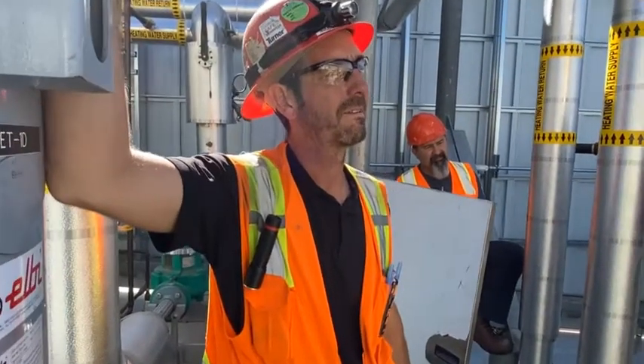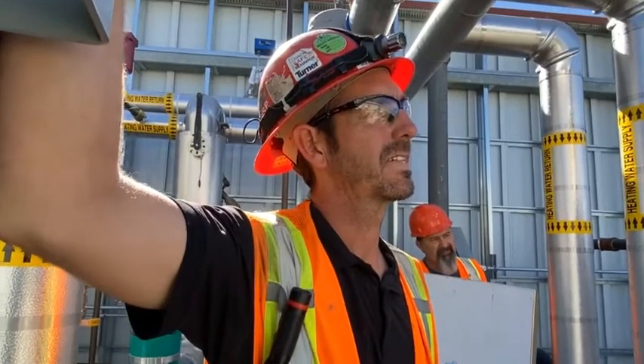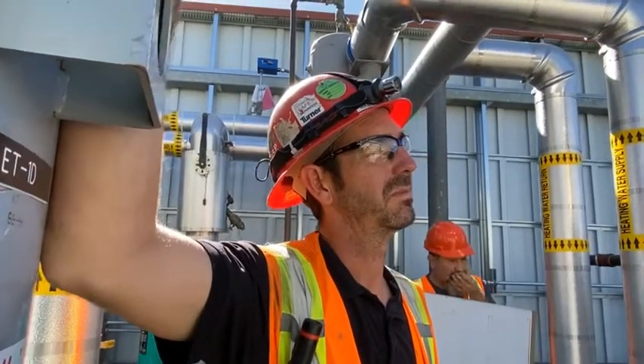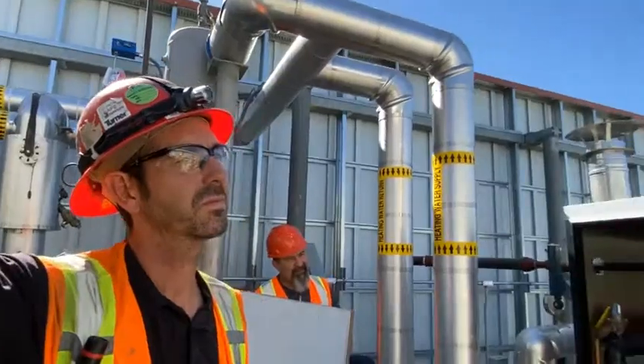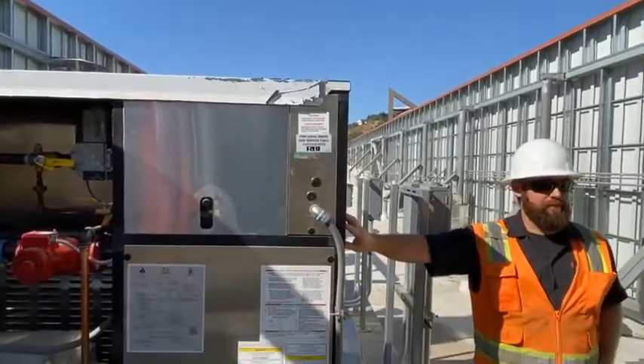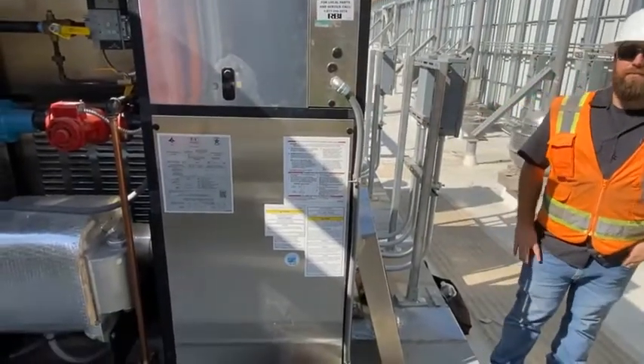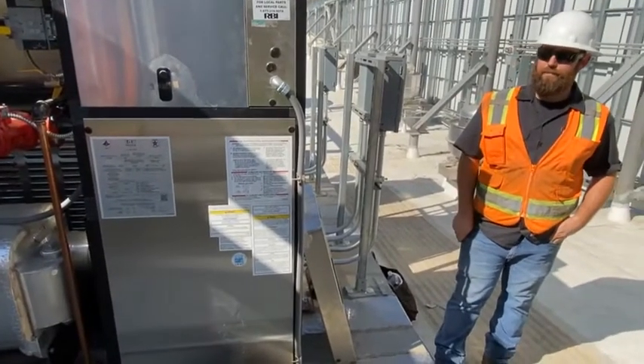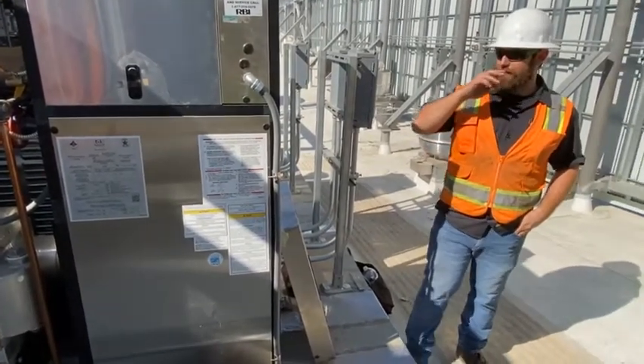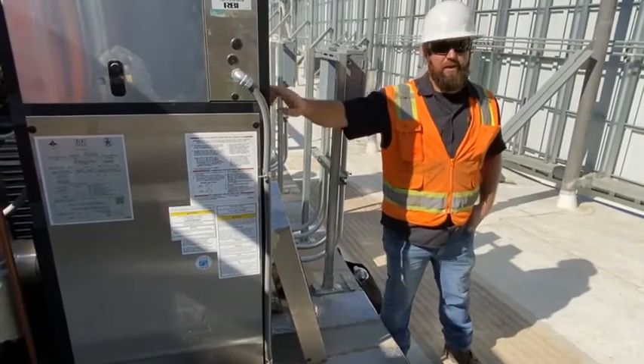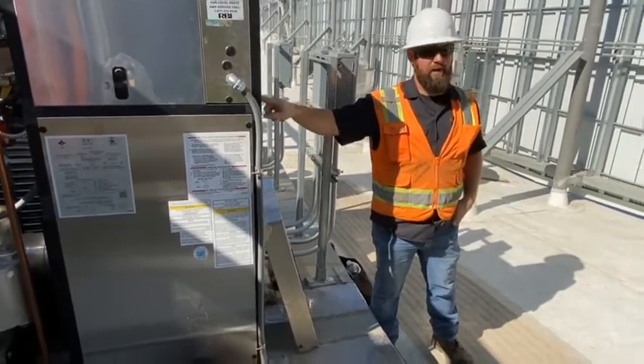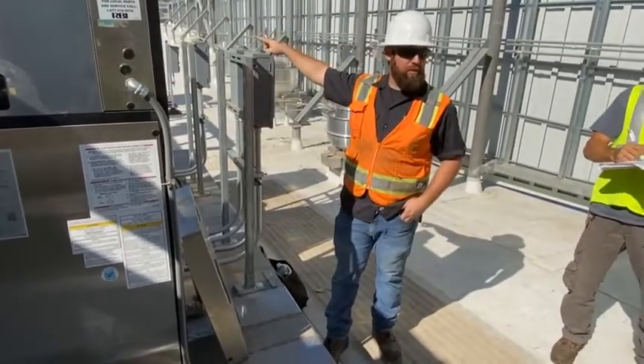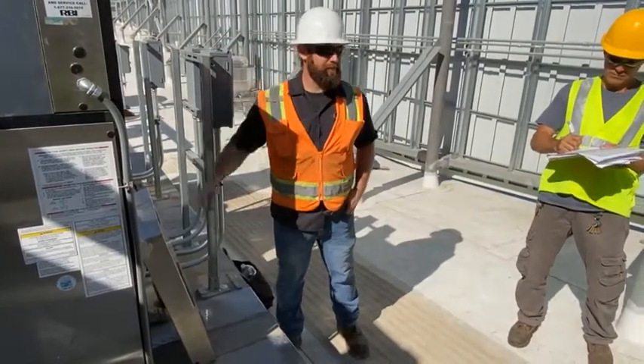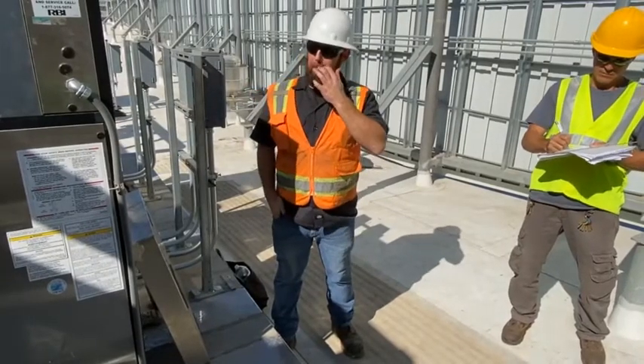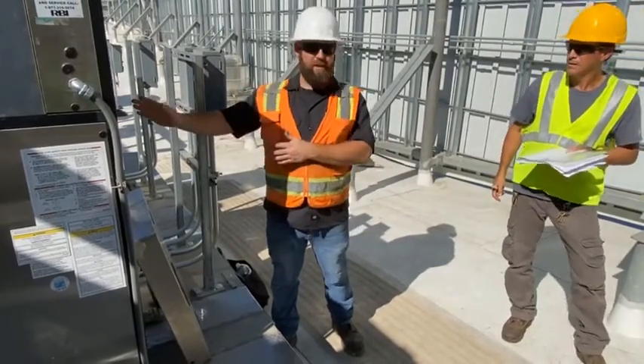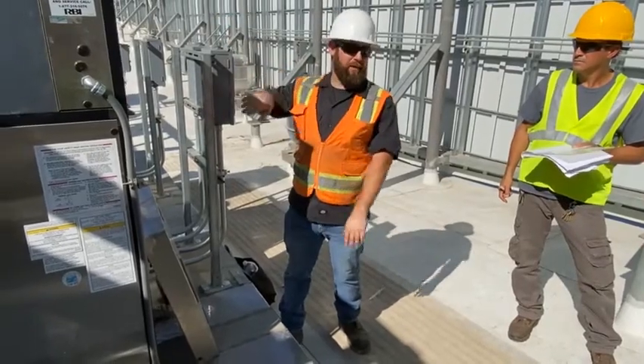Yeah, they'll work off its inlet temperature. Okay. But if this one goes into fault, there's a flame failure and it's not running, these two will still run off of this command. Okay. So you don't have to worry about that. Only if you lose power, if the power gets turned off. Right. And I believe if this loses the BMS communication, then they'll automatically switch over to local mode, which will still control these two boilers at this local set point. So just if you lose any power to this, then these two aren't going to run unless you put them into local.